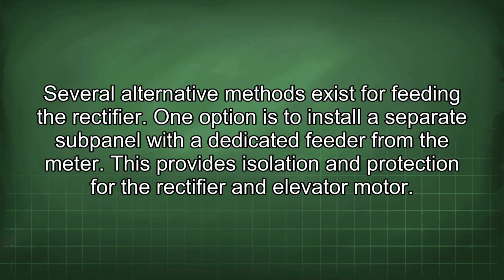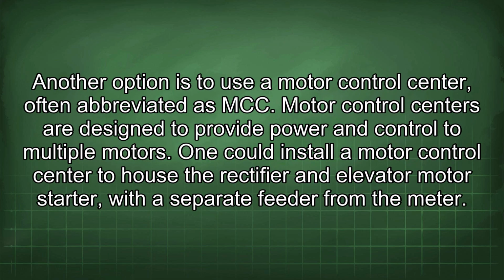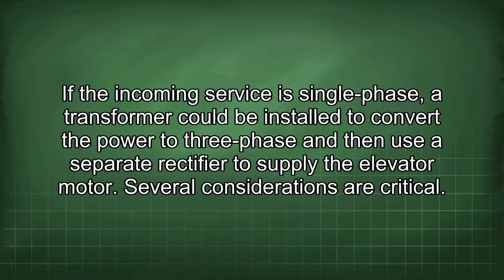Several alternative methods exist for feeding the rectifier. One option is to install a separate subpanel with a dedicated feeder from the meter. This provides isolation and protection for the rectifier and elevator motor. Another option is to use a motor control center, often abbreviated as MCC. Motor control centers are designed to provide power and control to multiple motors. One could install a motor control center to house the rectifier and elevator motor starter, with a separate feeder from the meter. If the incoming service is single-phase, a transformer could be installed to convert the power to three-phase and then use a separate rectifier to supply the elevator motor.